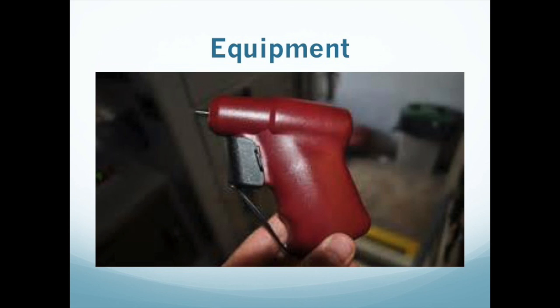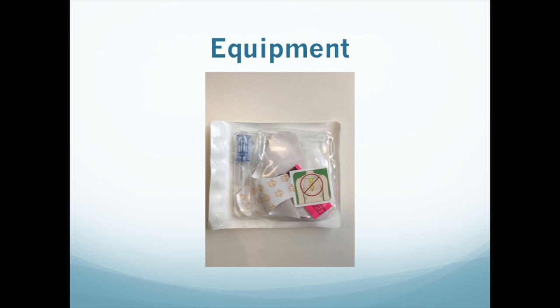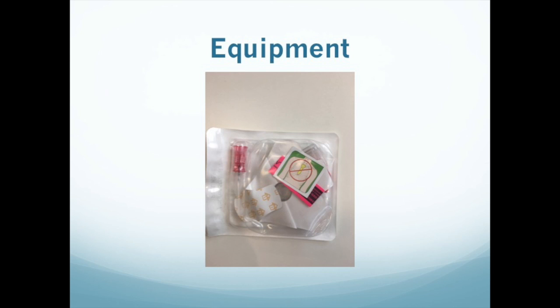The EZ-IO is drill-inserted, so you require an EZ-IO power driver along with an appropriate sized needle set. The yellow needle at 45 millimeters is for insertion into the humerus or in those patients with excessive tissue. The blue needle is 25 millimeters and is for adult patients greater than 40 kilograms, and the pink needle at 15 millimeters is designed for pediatric use.